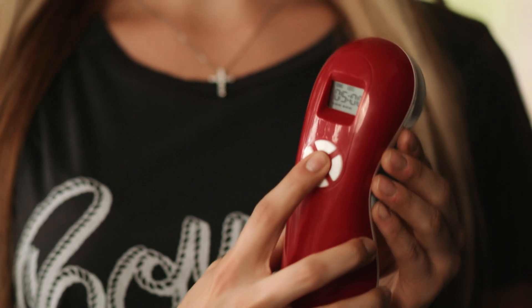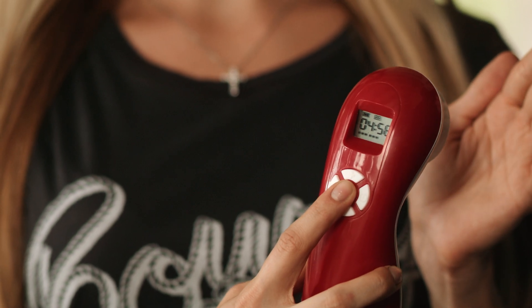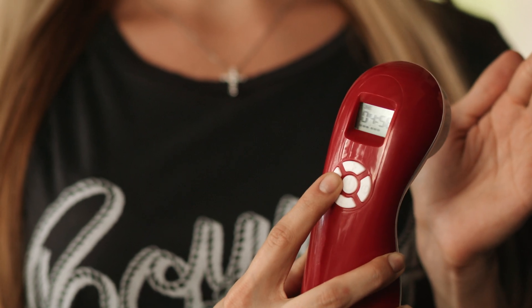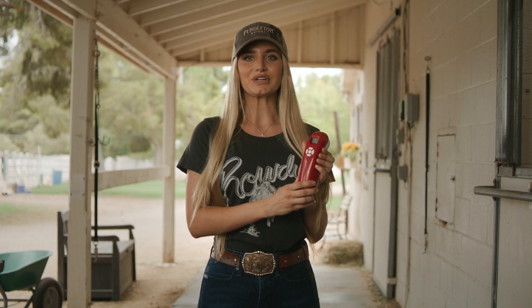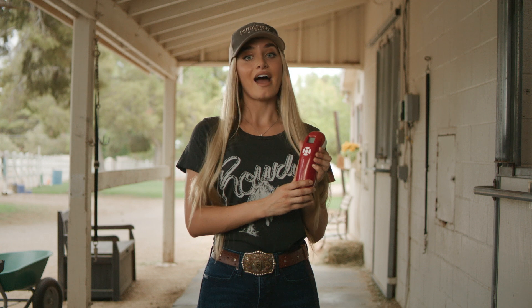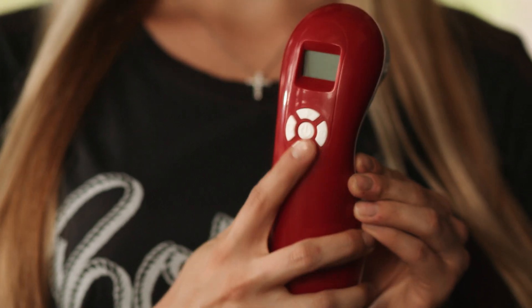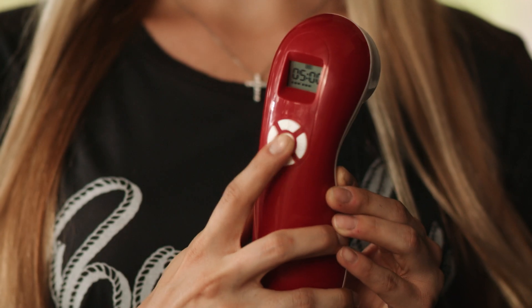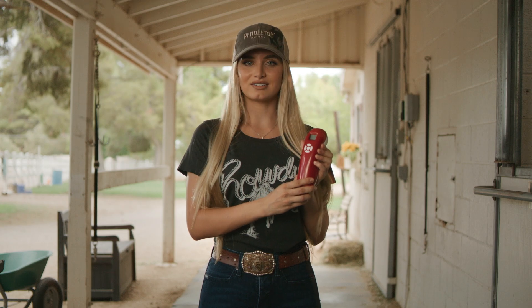With your time and intensity output set, you can get to work. Press on and off to commence output of the laser. You'll hear the buzzer beep and see time beginning to count down. Once finished, the laser will again beep and the LCD screen returns to setting status. At this point, the laser will stop outputting. Should you need to pause your laser in the process of using, just make a short press of the on/off button. You will hear the device beep and see your time pause.